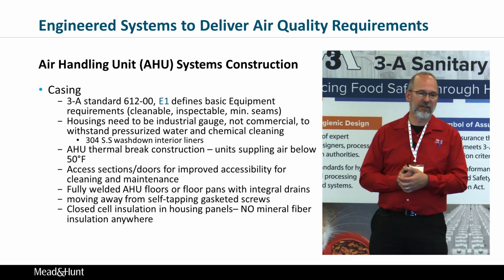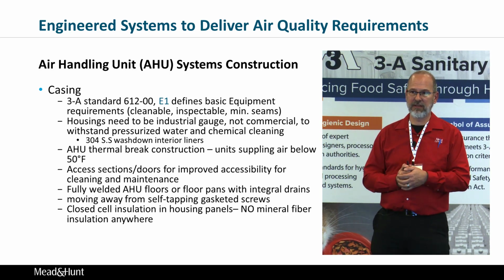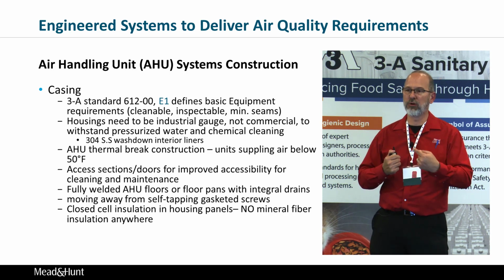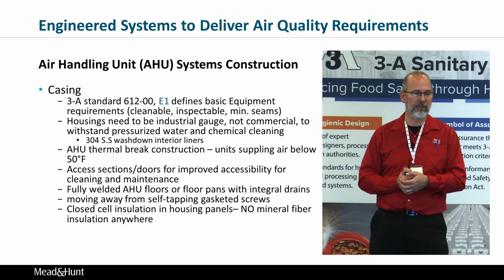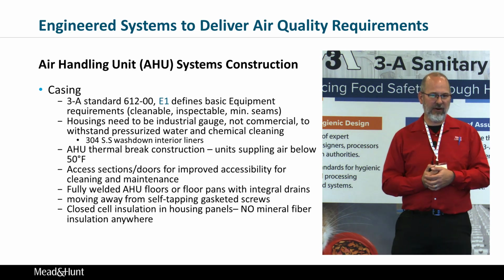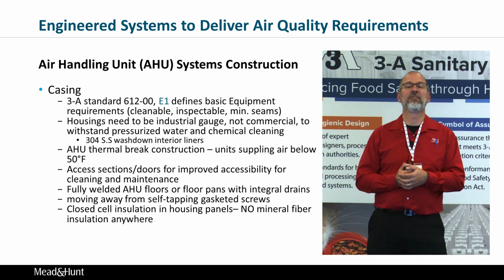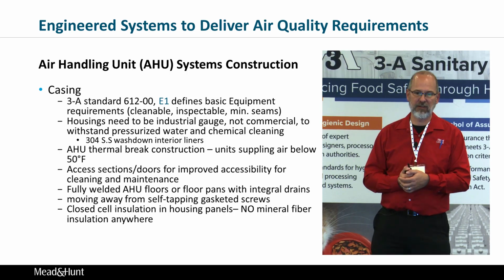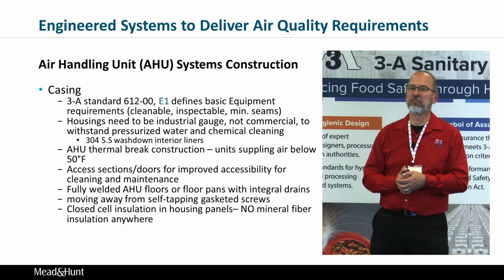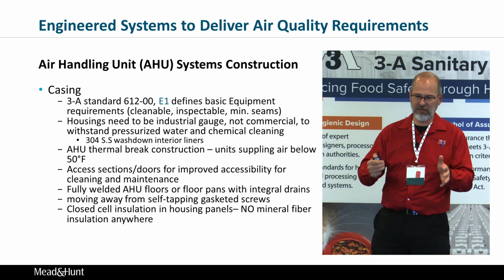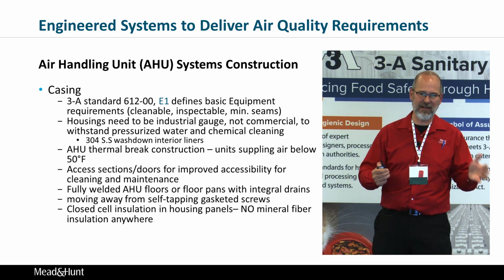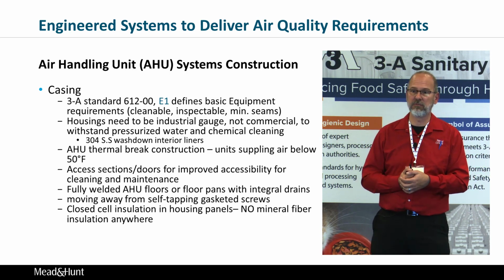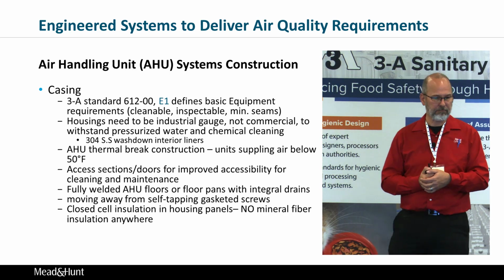For low temperature air handlers, you want thermal break construction. You don't want the inside or outside of the unit sweating if you're dealing with a low temperature condition. So the casing is designed to not have any thermal bridging between the inside and outside skin. Air handling units in food plants have lots of access doors. That's one of the reasons why the units are so large, is because every major system component in the unit has got access on the downstream and upstream sides of it to clean them. So lots of access doors.